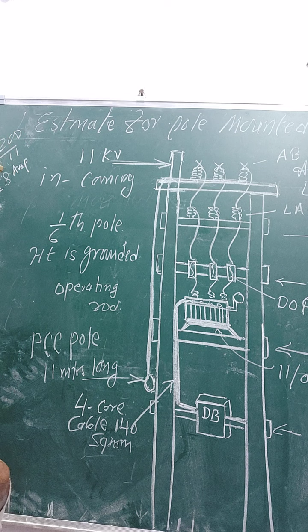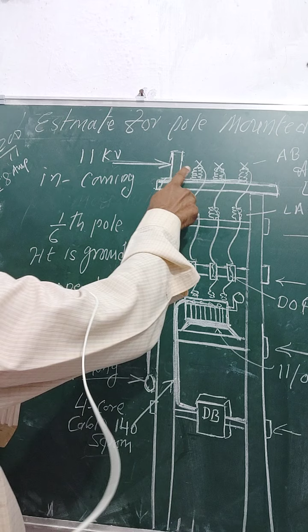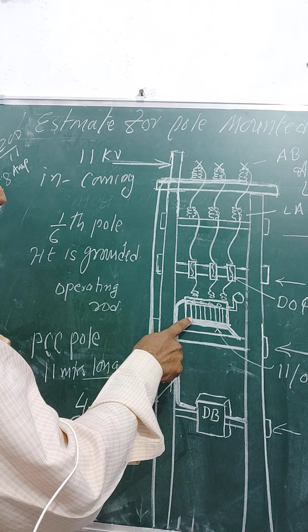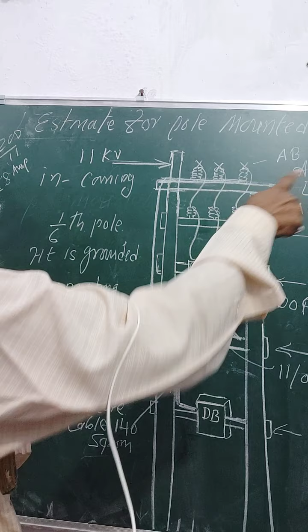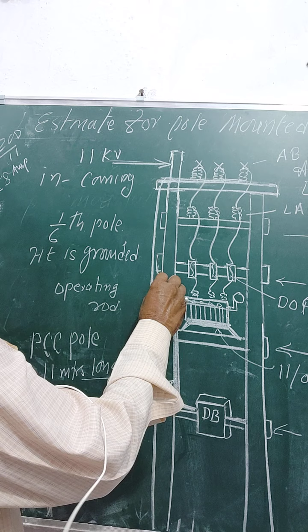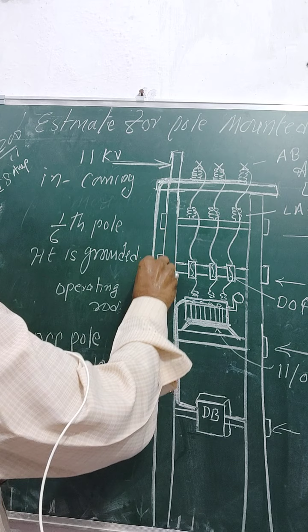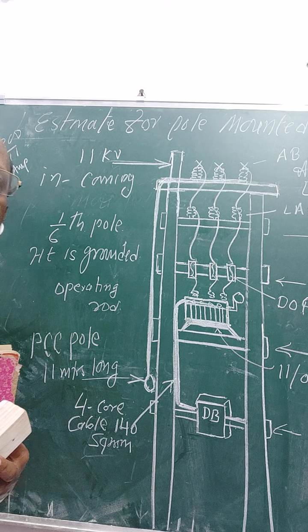So the diagram portion is over. It shows AB switch, lightning arrestor, DO fuse, transformer and distribution box. Channel iron size is given for every item, and this is mounted on a PCC pole, and this is the operating rod, so that the AB switch can be operated for opening and closing the circuit. So this is the complete diagram, you can see from a distance, with all dimensions readable, and you can have that particular diagram for the pole mounted substation.